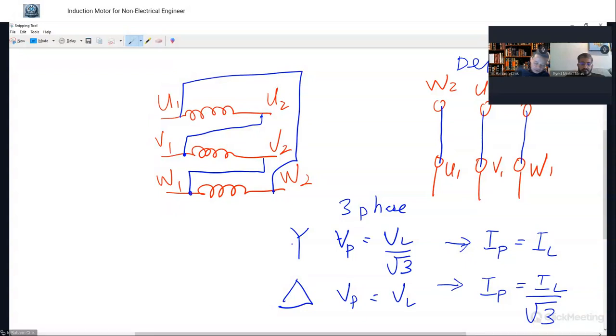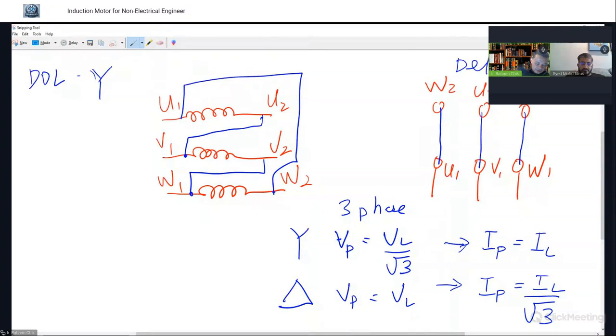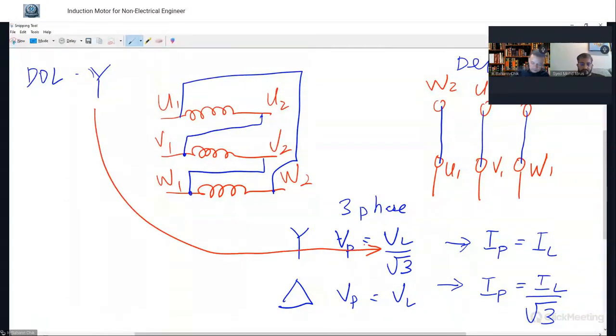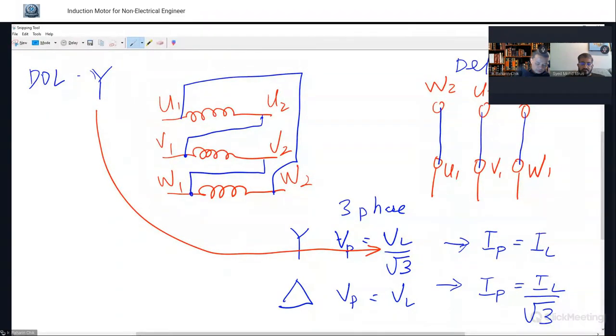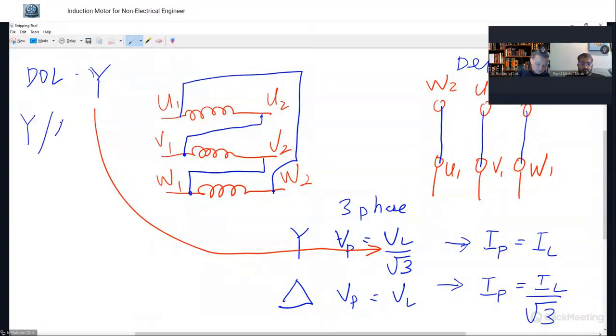Now, when you have DOL, you are connecting the motors in star. So the phase voltage is actually this one, right? The phase voltage is actually V line divided by square root 3. That means you are starting at reduced voltage, right? Now, if you are having star delta connection, when you start the motors, you are using star, and then when you run it, you get the full voltage, but the current is lower.